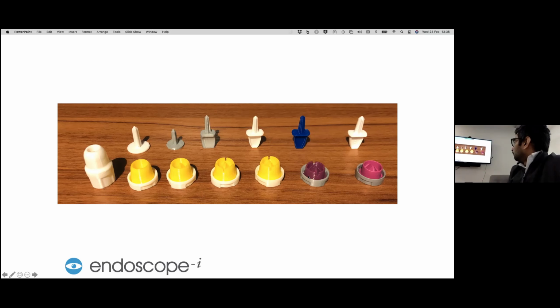But unfortunately, when you got really thin valves, so if we made this too thin, it looked great, but actually it was very fiddly to click it into place, and it also meant that once you pass the scope through, it would be quite easy for the inside element to drop off, which we certainly didn't want. So this was a compromise in height after a lot of testing of different heights of valves, but you can see we've kept with the crosshair arrangement. And we knew that this crosshair arrangement was simply a 3D printing process step rather than something that we were going to keep into the final design.